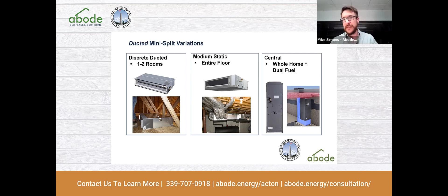So now I guess we'll get into a little bit of the technical detail and a little bit of the proof. Can a heat pump really be used in our climate? All right. So all of the major manufacturers have products that we would refer to as a cold climate air source heat pump with no capacity drop off. So that means it's a 36,000 BTU unit at 47 degrees. It's still a 36,000 BTU unit down to the single digit. So at no point does it lose its capacity. Mitsubishi makes this product, Fujitsu makes this product, Bosch, LG, Daikin, Trane, Carrier, like every single manufacturer has this type of product ready to go.